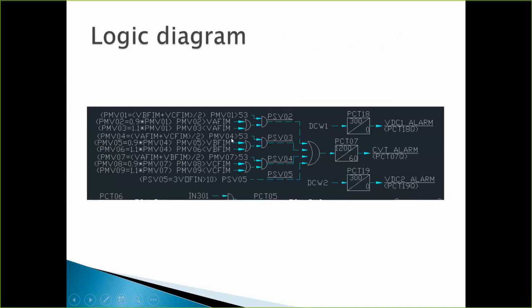This drawing is a little bit better, okay? This is B phase, C phase. I've averaged them, okay? Is it greater than 53 volts? I fire an AND gate, all right? I take A phase. Is it 10% above or below? If it is, that satisfies the equation. That hits the AND gate. That's one input. I did the same for the other phases. I hit a timer. Boom, I have an alarm, okay? Make sense? Same thing for A to C, same thing for A to B, okay? It's the average. Is it 10% above or below the phase that you didn't measure? And then if it satisfies the AND gate, boom, it's an alarm.